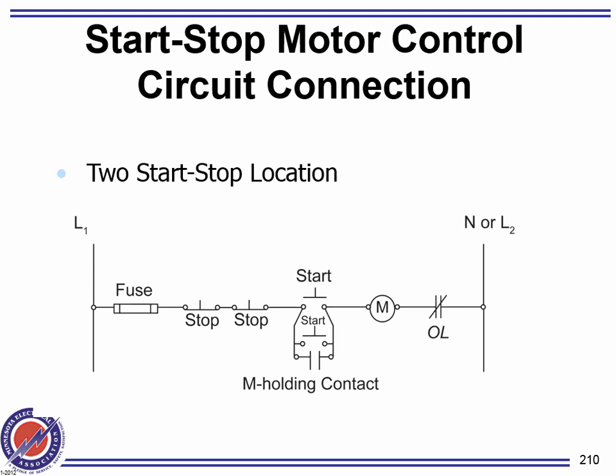Now, you guys remember the three-way and four-way switches that we use so you can turn things on and off? You use them if you're using high voltage switches. If you're using low voltage switches, do you need them? No. Low voltage switches drive a magnetic contactor, drive a power pack, which is a relay basically. You can have 100 low voltage switches driving the same contactor in a power pack.